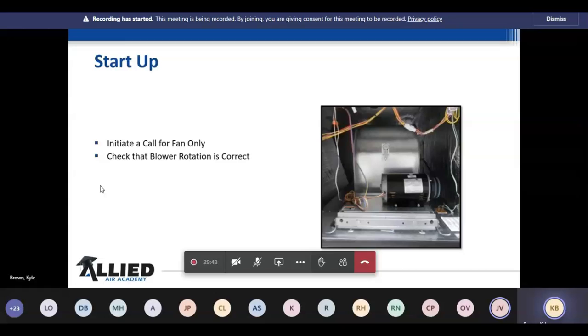So if a technician comes up behind another one and doesn't know, and they look at the wiring diagram and see it should be red, blue, yellow, but it's yellow, blue, red on top of that contactor, they go, well, this has a factory problem and it's wired wrong from the factory. That may not be the case. It may just be the wrong rotation. I would suggest, and I realize this is not going to happen too often, to write on this blower rotation corrected and then put something on there if you're going to do it that way.